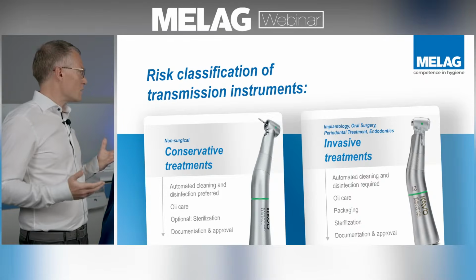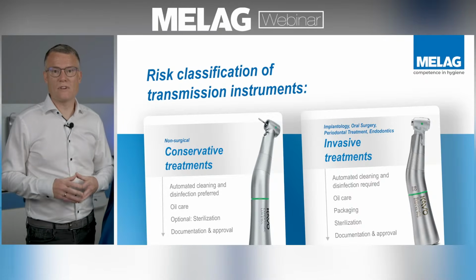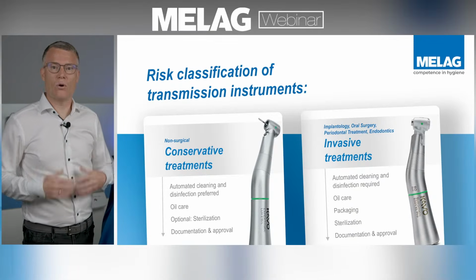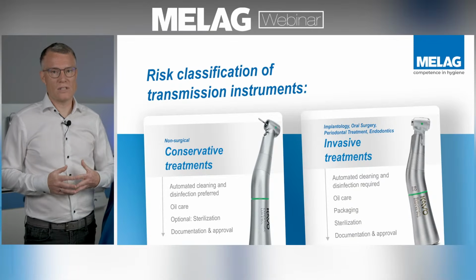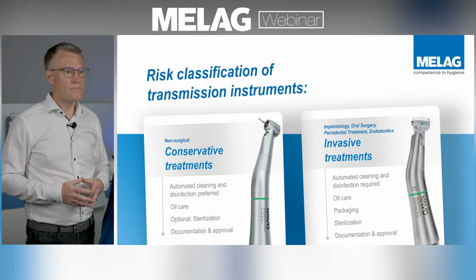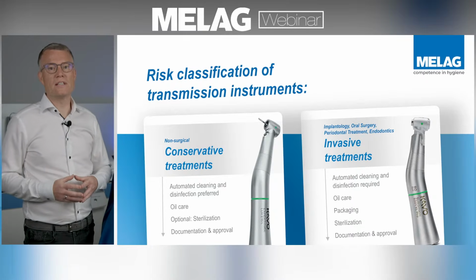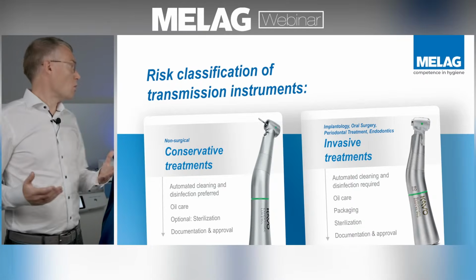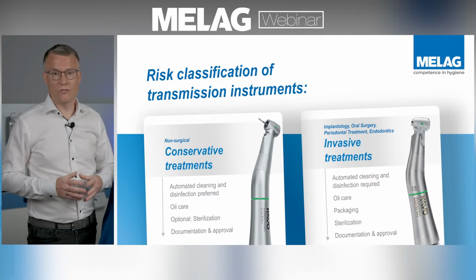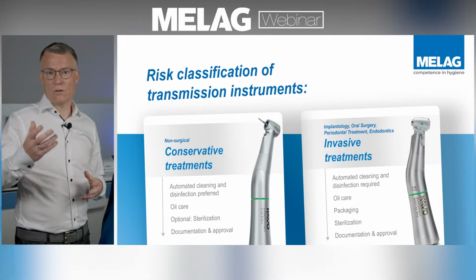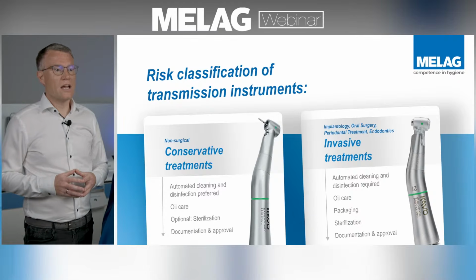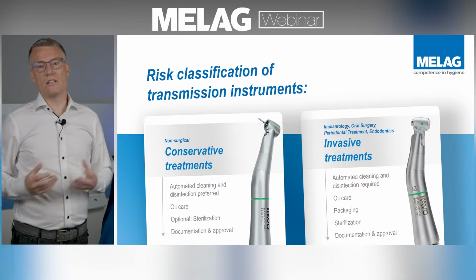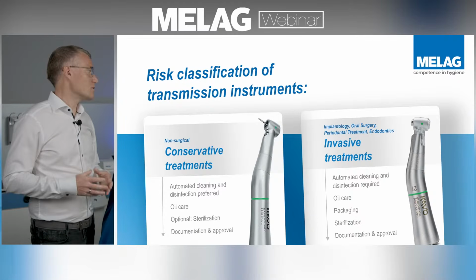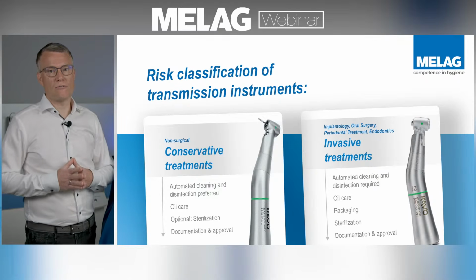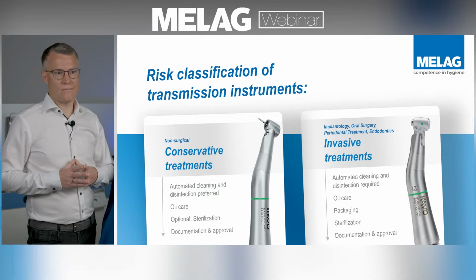It all starts always with a cleaning and disinfection. And the automatic solution is definitely the preferred option. After the cleaning and disinfection, you should oil, lubricate, take care of your instruments inside, but also the important chuck care. And optionally, there might be a sterilization, and last but not least, a documentation and approval of the things you have done. Yes. Right.